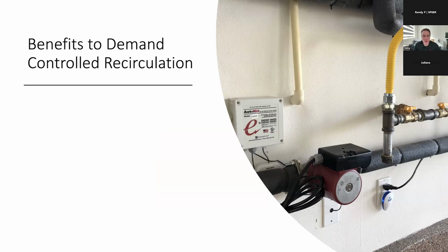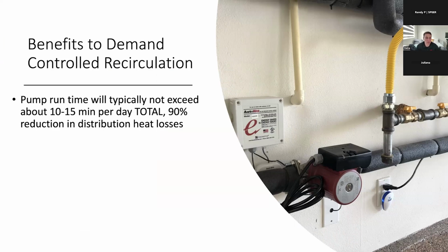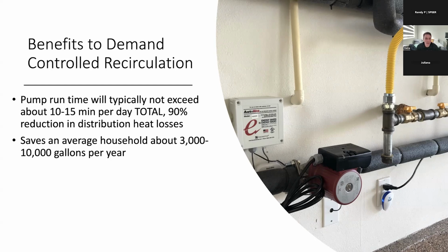So what are the main benefits of demand controlled recirculation? Well, number one, first and foremost, you're limiting the runtime of the pump to only when it needs to run, because you're looking at temperature and you're looking at demand. So again, you're only going to see about 10 to 15 minutes of runtime per day in total. So you're going to have more than a 90% reduction in distribution heat losses compared to systems that are just running that pump all the time. You're going to save somewhere between 3 and 10,000 gallons of water per year by not having to wait for that hot water.